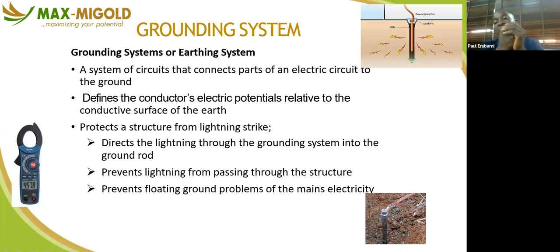Electricity comes with heat. Why do you need to service your earthing arrangement? Because as that heat is produced, going through where it is buried, it starts to form a carbon deposit. It starts drying up, just like your charcoal, and it becomes a resistance. So with time, it will not allow the passage of electricity easily. At some point, it will block it. So that current is retained in your installation. You start paying high bills because that circulating current is there. It has no way to escape.